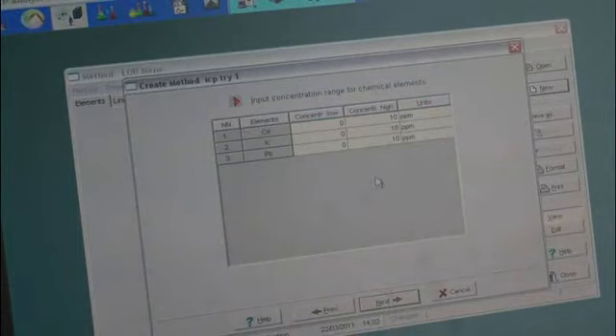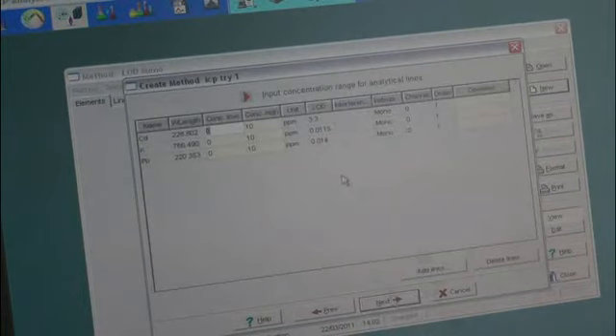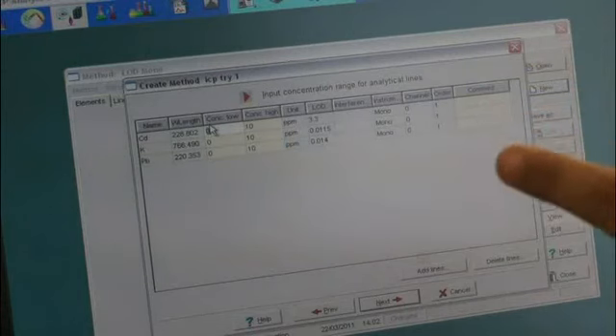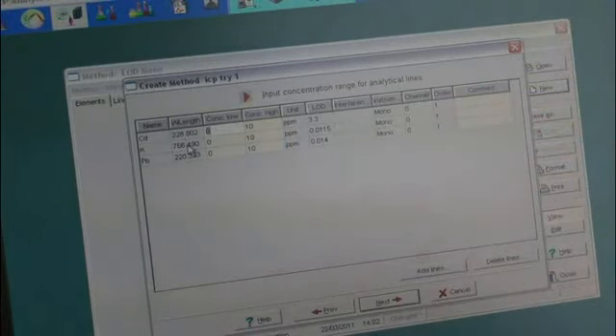Now that's just a range. It's not your standard, so you can leave that alone. What it does is in the analysis, it'll just make that box red if it's out of that range. And there you choose what wavelengths you want to analyze on those elements. You could either delete or add lines there. Like the potassium line, that's the most sensitive one. Potassium doesn't have very many. And lead, that's the most sensitive lead line. The cadmium line we use is 226 for checking it.